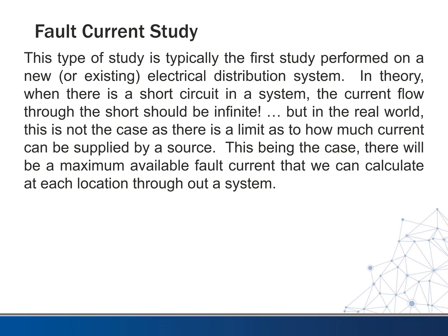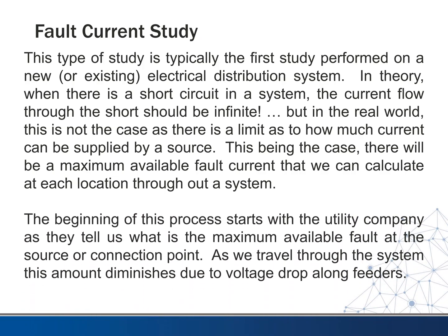So we need to know what that available current is, and how it changes through our system. There will be a maximum available fault current that we can calculate at each location throughout our system. This process starts with the utility company, as they are going to tell us what the maximum available fault is at the source or connection point — usually on the secondary side of their utility transformer. As we travel through the system, this amount is going to diminish due to voltage drop along the feeder, so we need to calculate it all the way throughout our system.